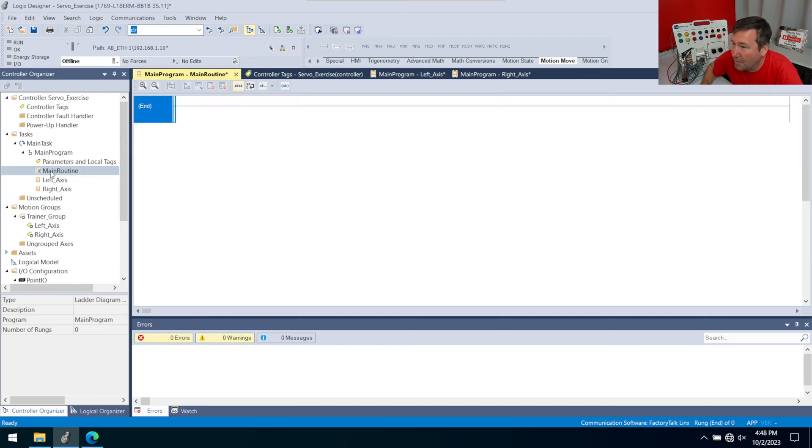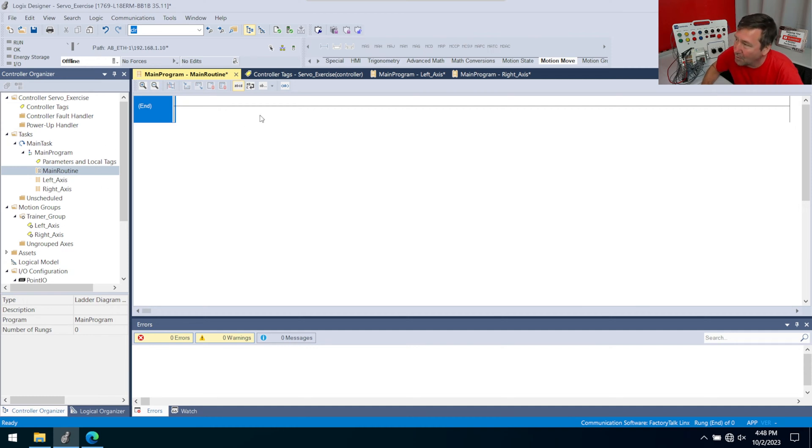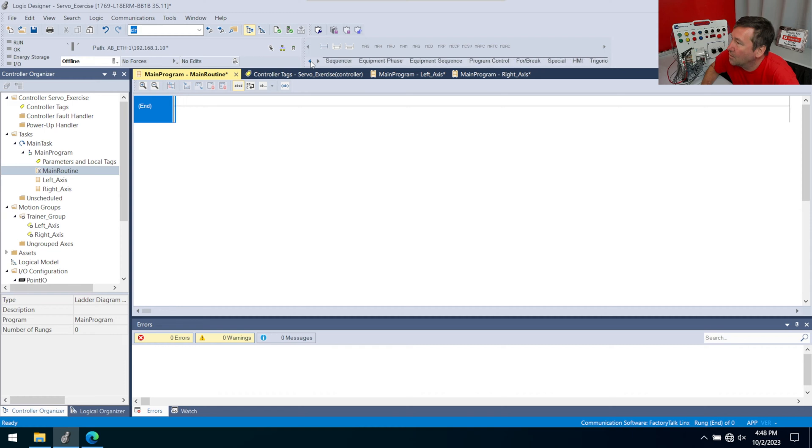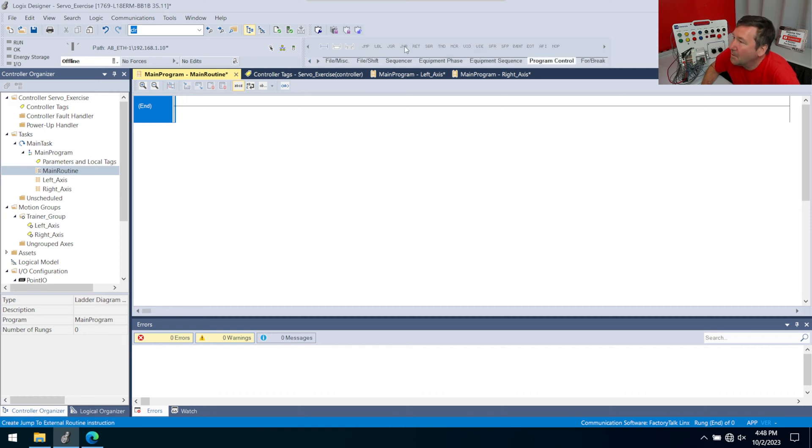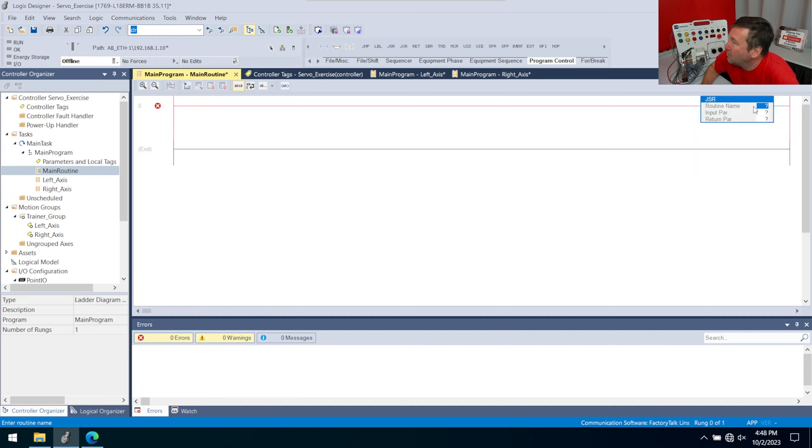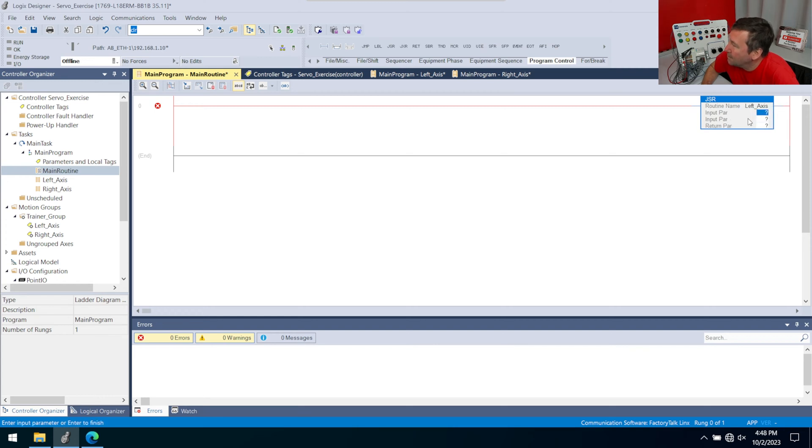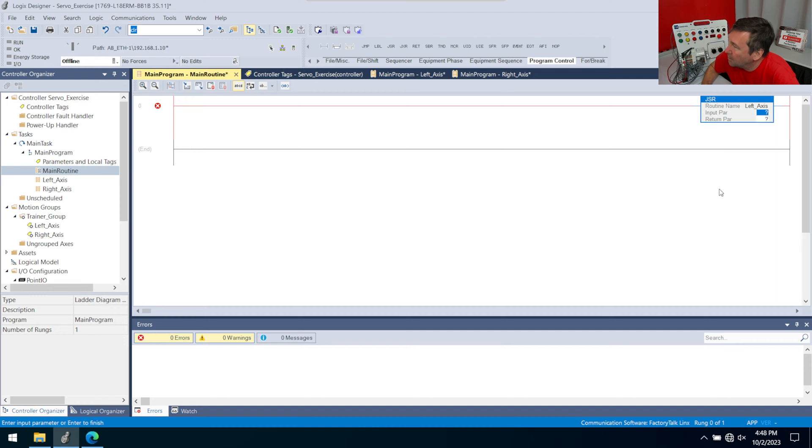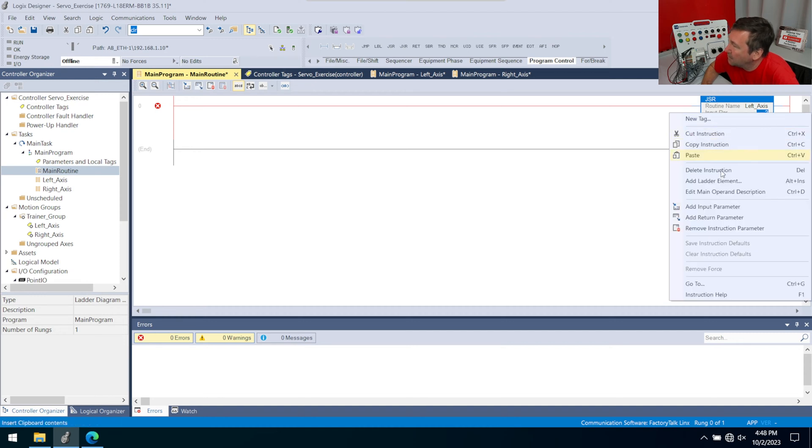And now let's get our main routine because we need to get JSRs to actually run these. We're not doing any type of real complicated program control here. We're just making some folder organization for ourselves. So let's go over to our program control. And we want this JSR. So bring a new rung down JSR. And we're going to go find our left axis. And notice it puts these input parameters in, we're not actually going to use those. So just right click, remove instruction parameter, right click, remove instruction parameter, right click and remove instruction parameter.